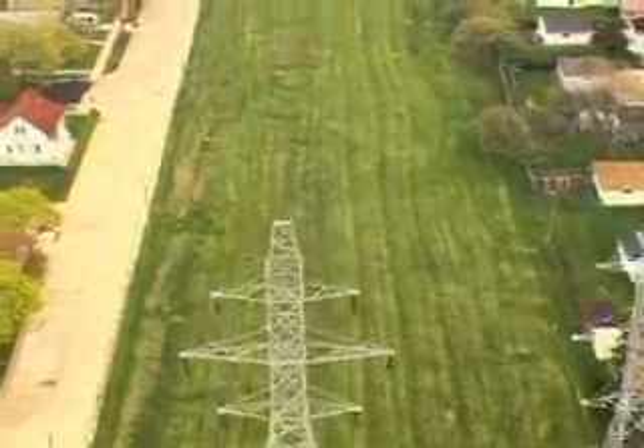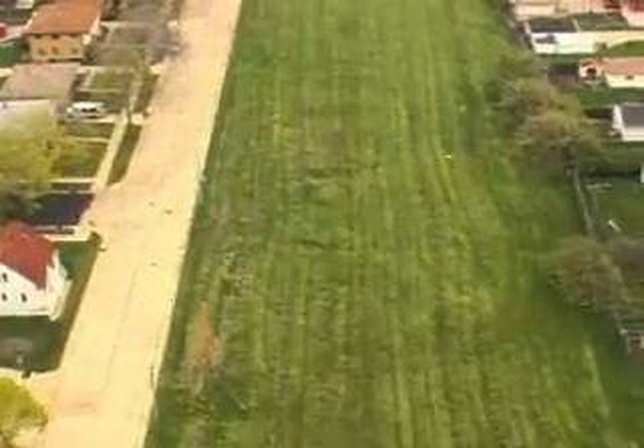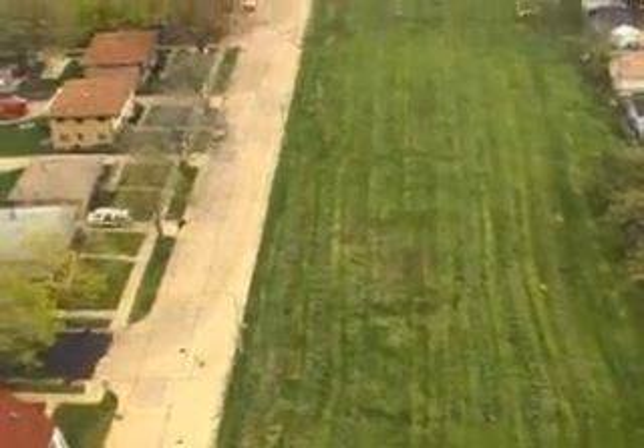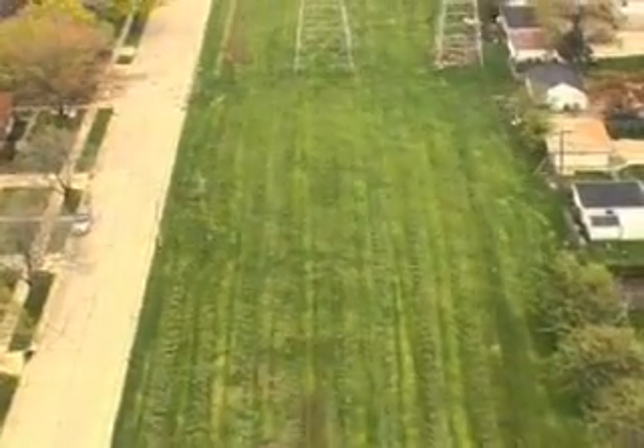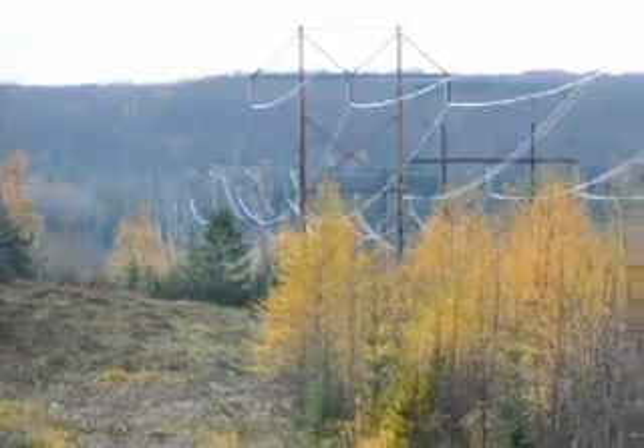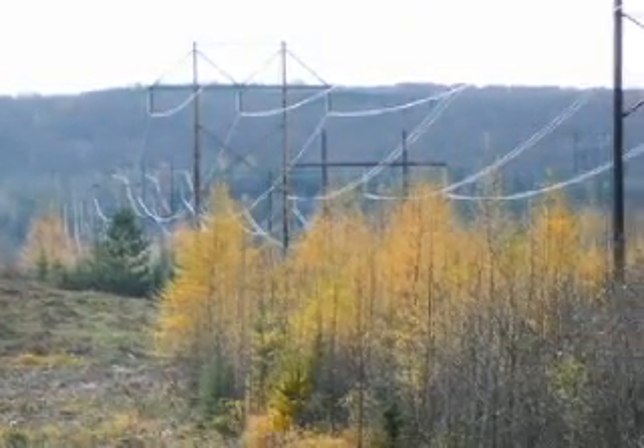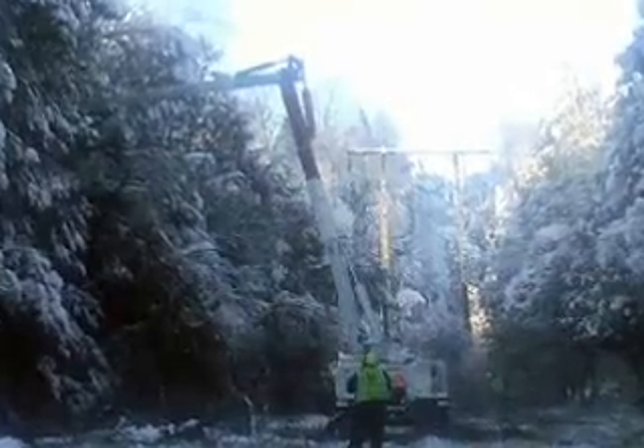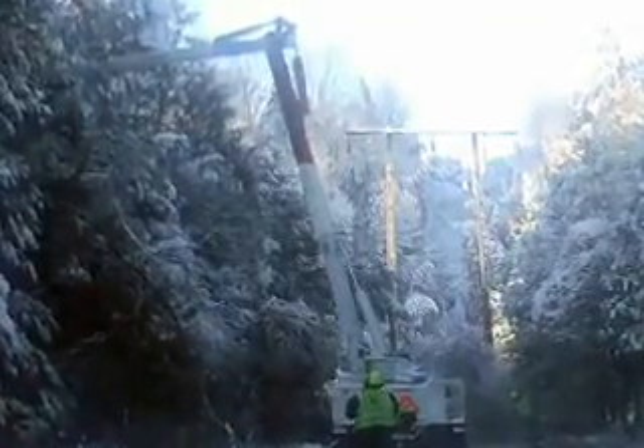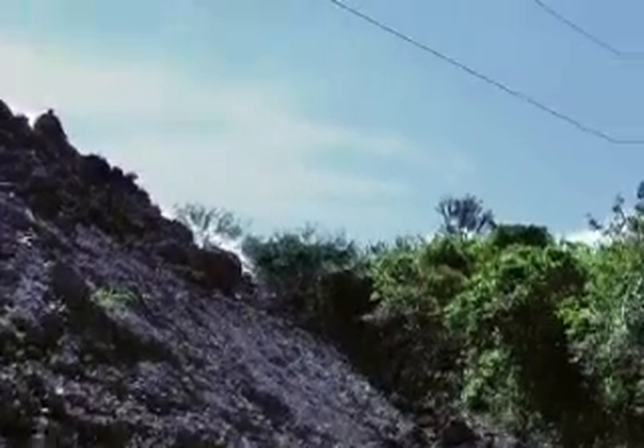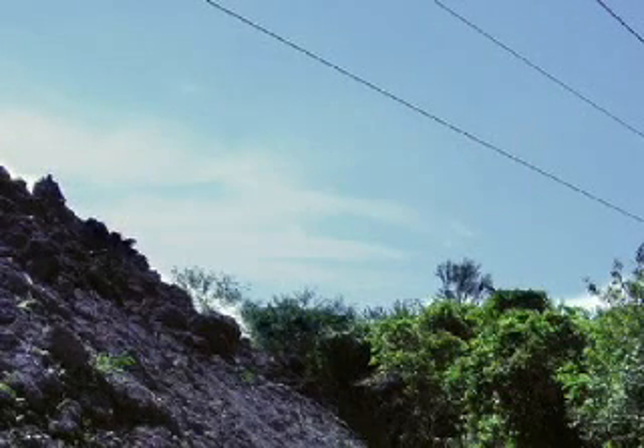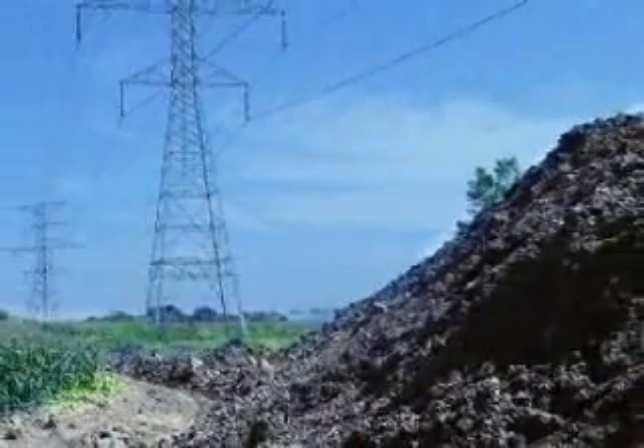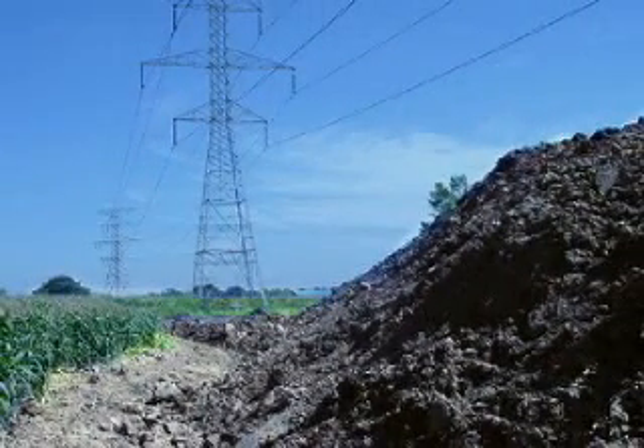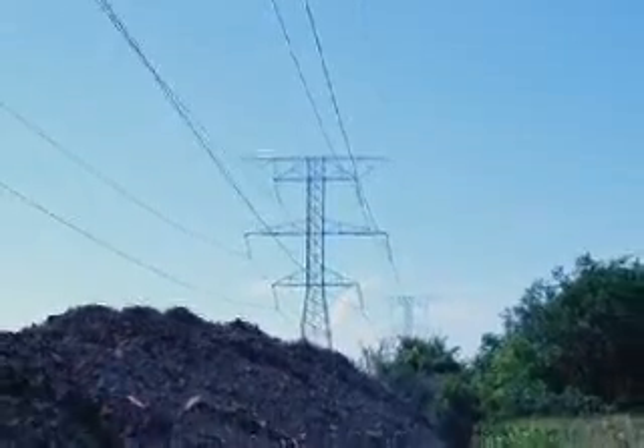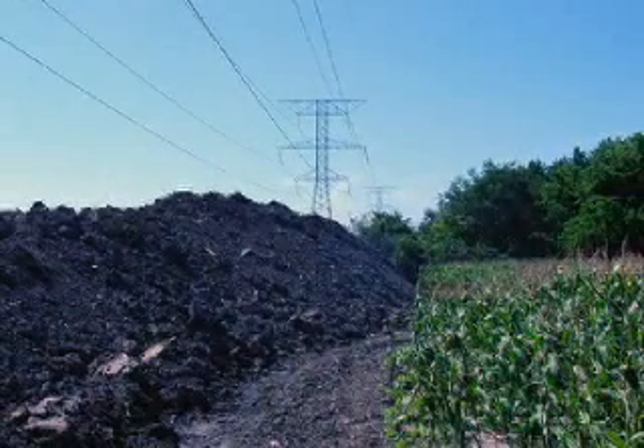Sheds, garages, swimming pools, septic systems, and other structures are not allowed to be constructed in the right-of-way. Wisconsin state law prohibits construction of homes beneath an electric transmission line. Trees and shrubs can also obstruct access to the transmission lines and structures. If a tree makes contact with the transmission wire, it can cause a transmission outage and may endanger those nearby. All of our transmission lines must maintain certain code clearances between the ground and the wires. Any change to the grade under the transmission lines must be reviewed prior to construction to make sure that we can maintain access to our facilities and that code requirements are met.